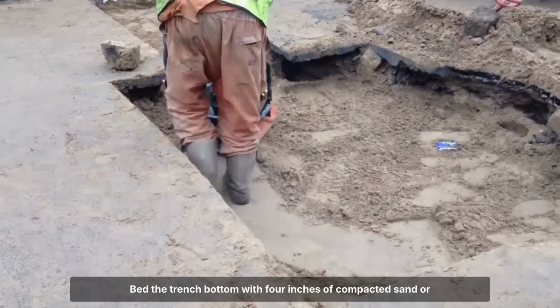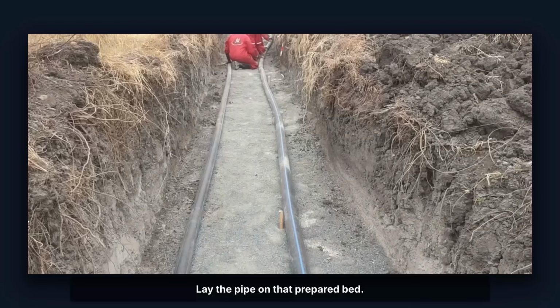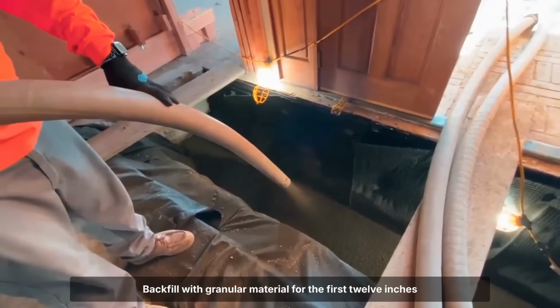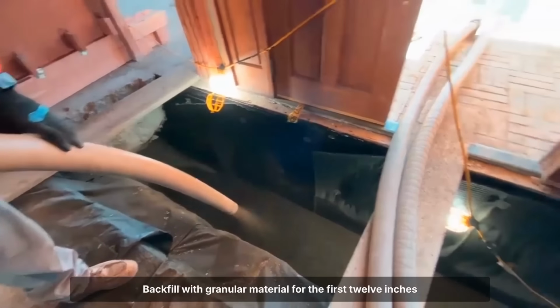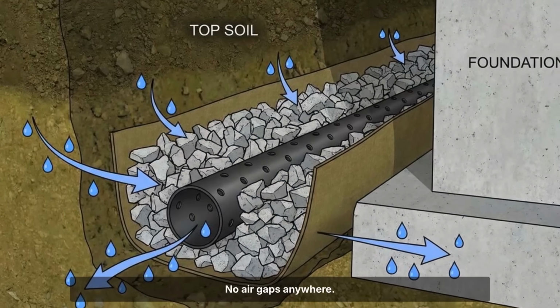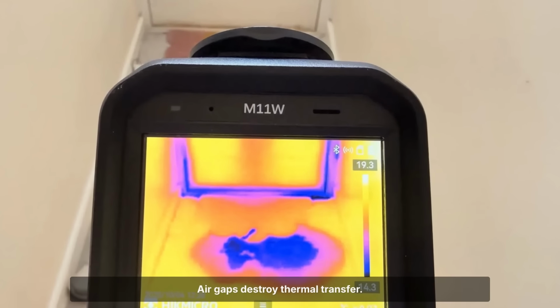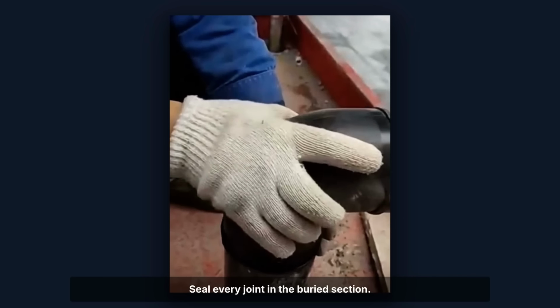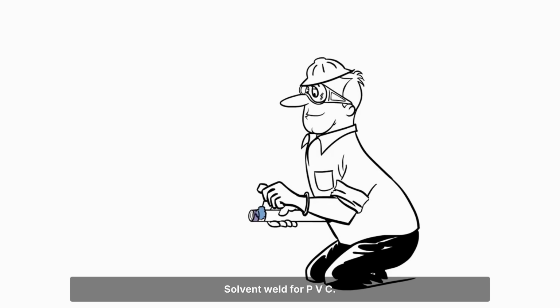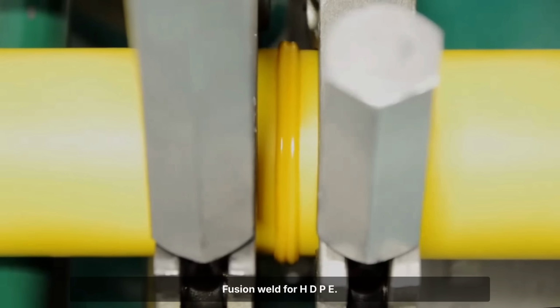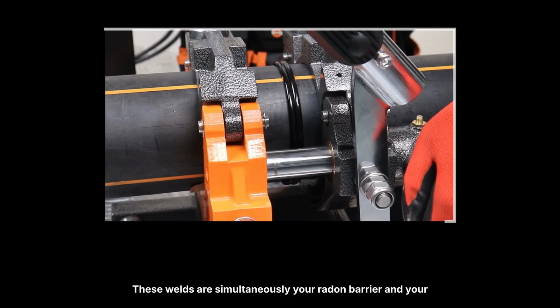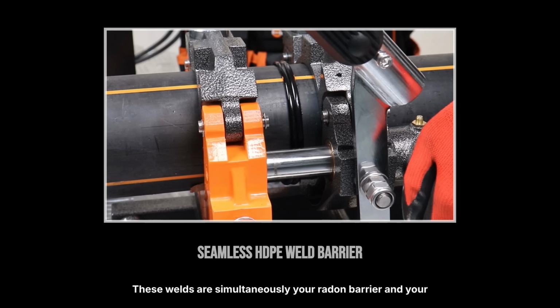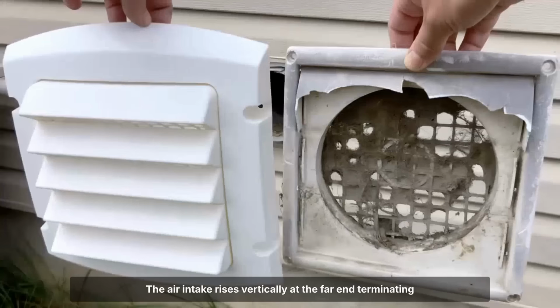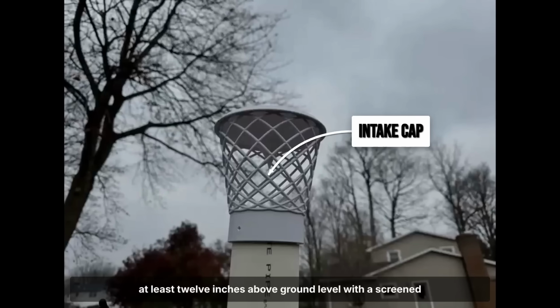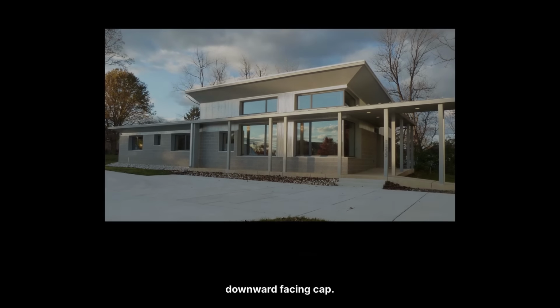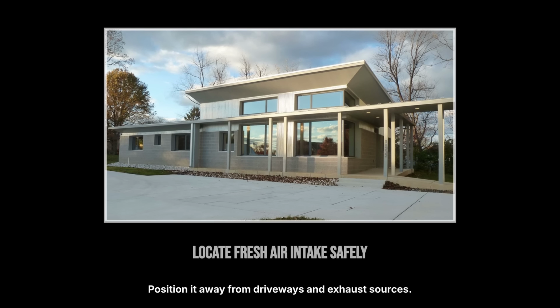Bed the trench bottom with 4 inches of compacted sand or pea gravel. Lay the pipe on that prepared bed. Backfill with granular material for the first 12 inches above the pipe, ensuring complete contact. No air gaps anywhere. Air gaps destroy thermal transfer. Seal every joint in the buried section. Solvent weld for PVC. Fusion weld for HDPE. These welds are simultaneously your radon barrier and your groundwater barrier. The air intake rises vertically at the far end, terminating at least 12 inches above ground level with a screened downward-facing cap. Position it away from driveways and exhaust sources.